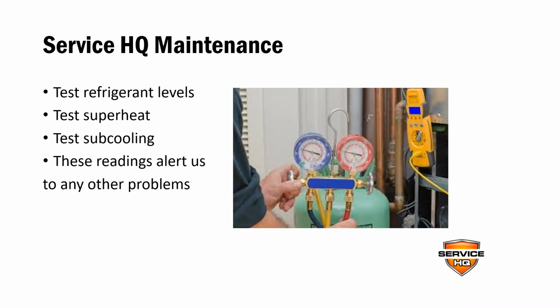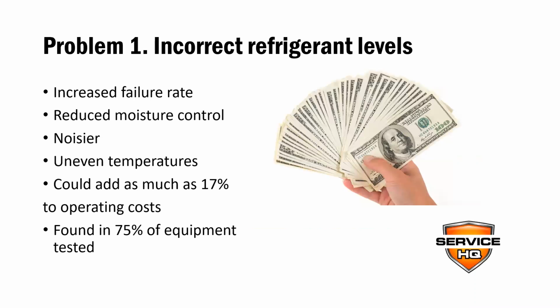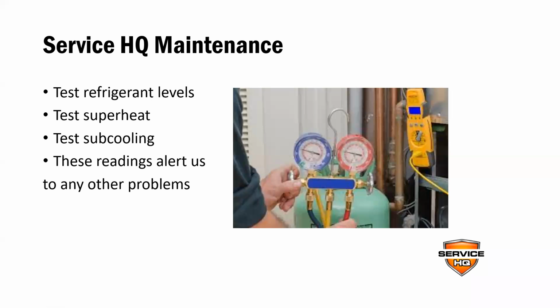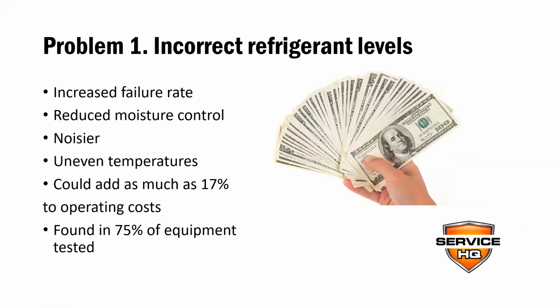So typically, there are two major problems that we find when we're checking refrigerant levels. Number one is just incorrect refrigerant levels. Like it's either overcharged or it's undercharged. That means there's too much refrigerant in it or there's not enough. And what these things cause is increased failure rate and reduced moisture control, meaning you're not going to remove as much humidity from inside the house, so it's a lot harder to stay comfortable.